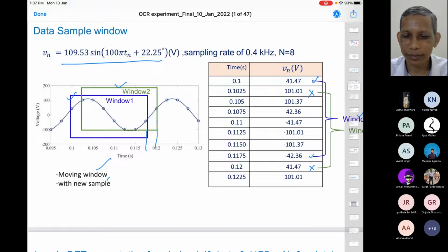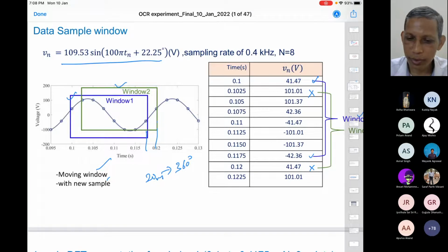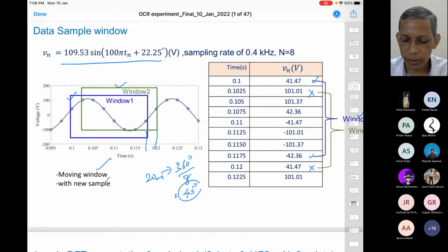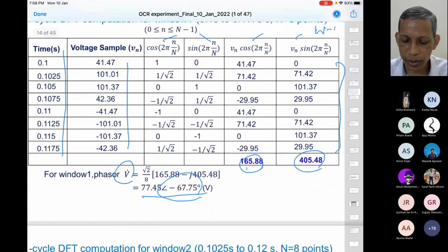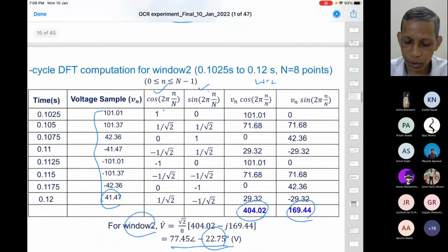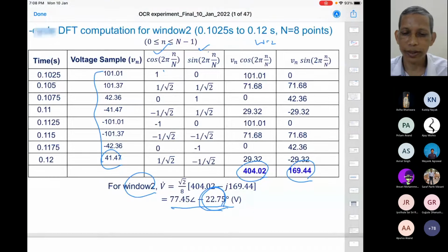Why 45 degrees? 20 milliseconds gives you 360 degrees. Now we have 8 samples, so 360 degrees over 8 samples. Every sample interval is 360 divided by 8, so we are getting 45 degrees. So that 45 degrees of advancement, from minus 67.75 to minus 22.75, is what we are getting. That means the phasor obtained from this is indicative of the angle also, correctly.